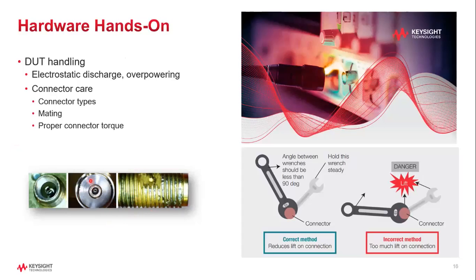You may say, oh, Daniel, this is okay because it's on the outer side, it will not give any problem. No, actually, that's not true. Even a slight dent will give a different reading, especially when you go to microwave or millimeter wave frequencies. Such a tiny dent gives a lot of errors or inaccuracy. So as an RF engineer, again, you need to know how to take care of the connectors and how to do proper mating. Can a type N mate into a 3.5 mm? Of course not. But can a 3.5 mm, or another name, SMA, connect to a 2.4 mm or even a 1 mm connector? So this is the knowledge that students need to know before they can be qualified RF engineers.